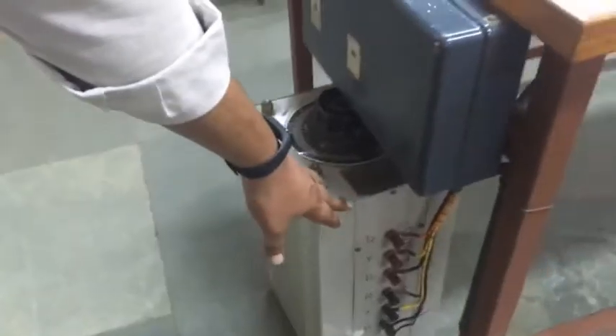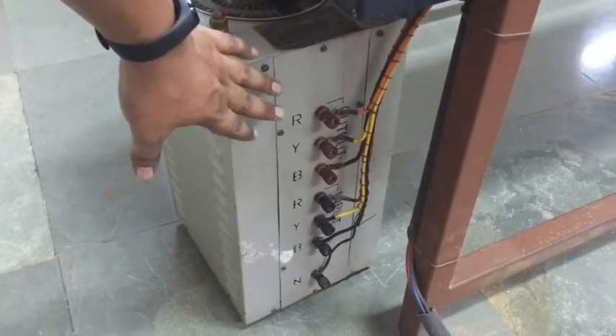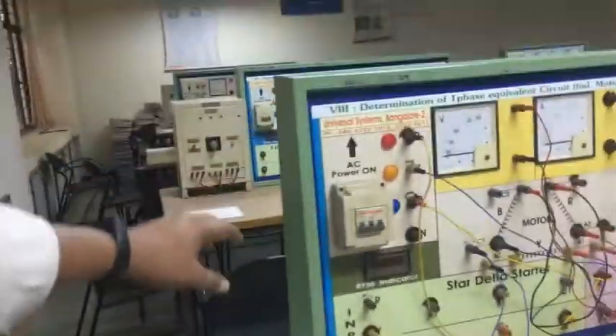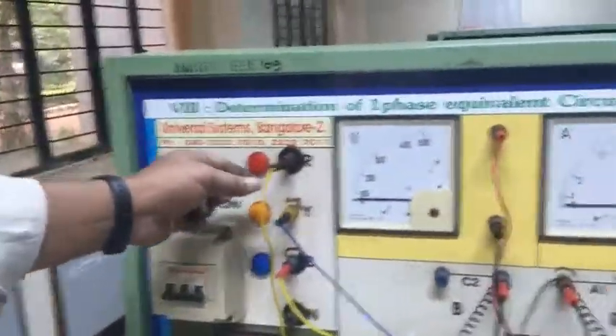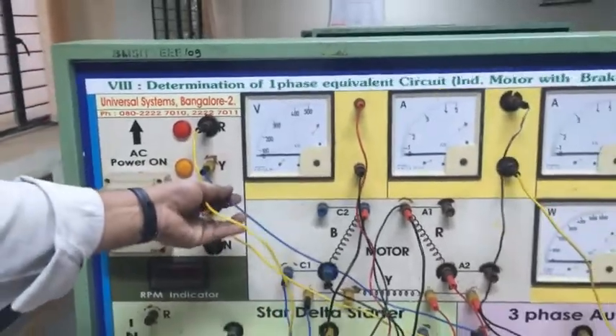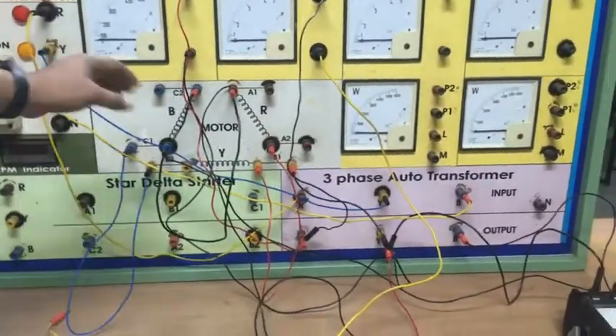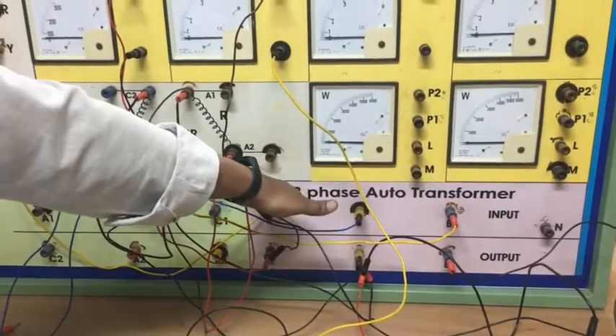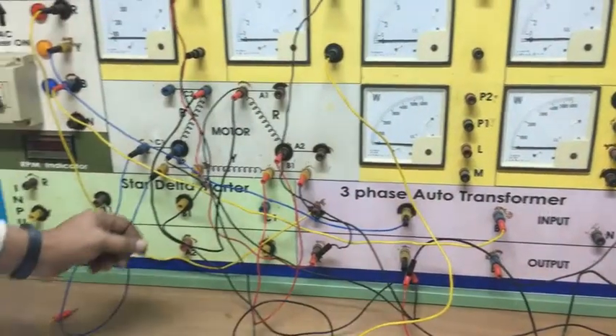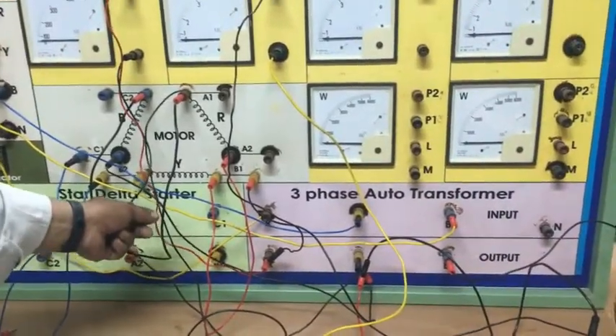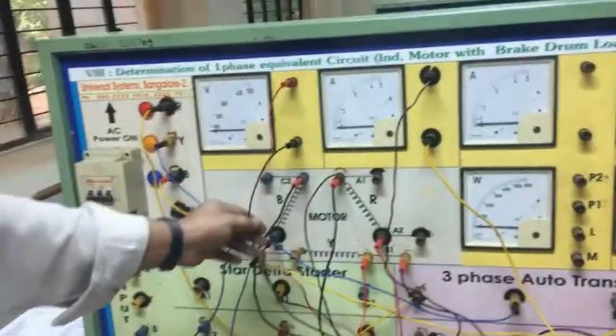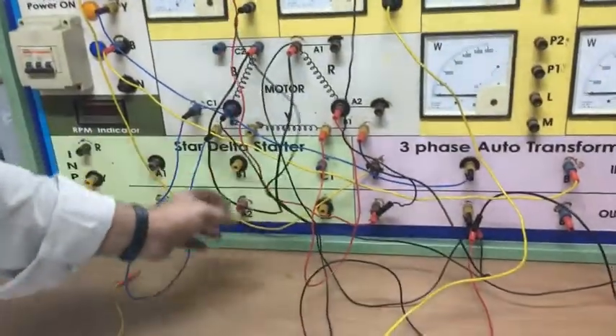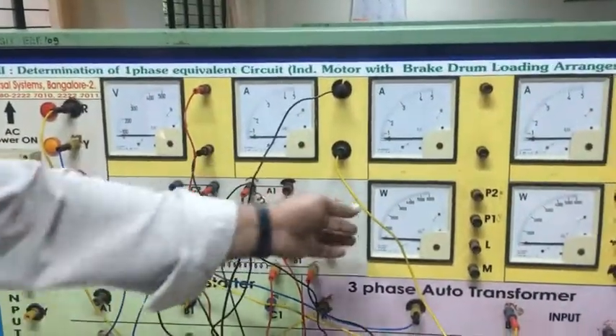While coming to the circuit on the panel board, here is the auto transformer, where all the input as well as the output connections have been done. From the panel board we are giving the input supply, that is RYB three-phase, to the input terminals of the three-phase auto transformer. Next, from the output terminal, as per the circuit diagram, the voltmeter will be connected between R and Y. And from R phase we are connecting to the ammeter, and next from the ammeter to the LPF wattmeter.